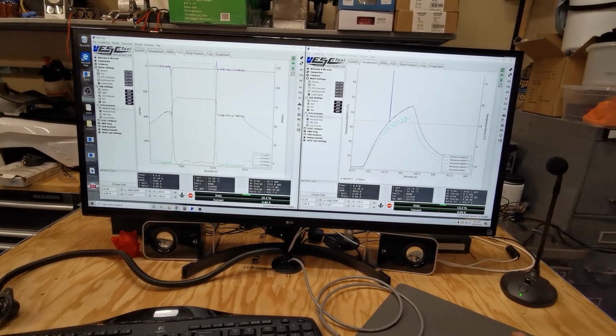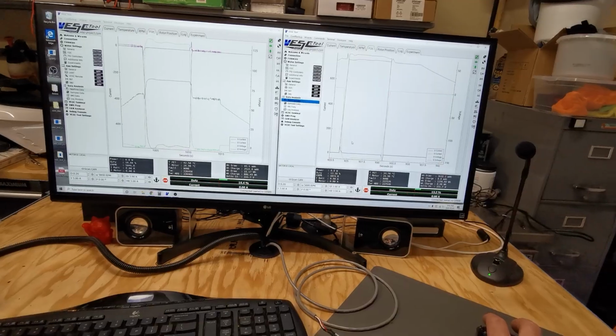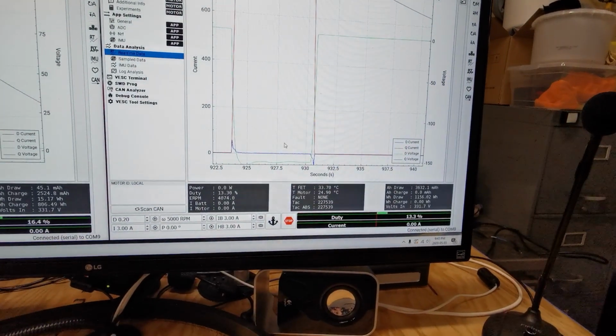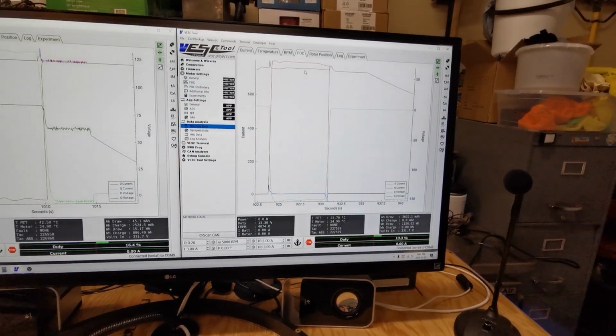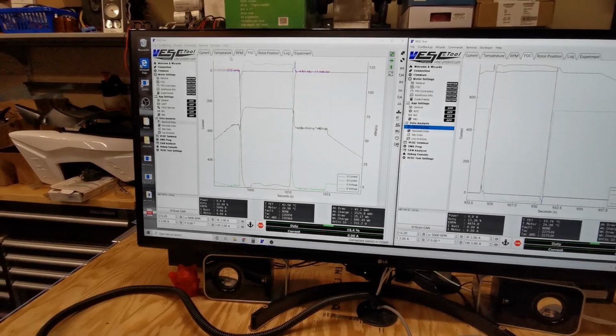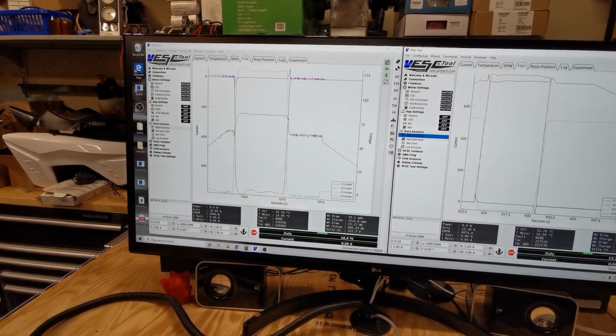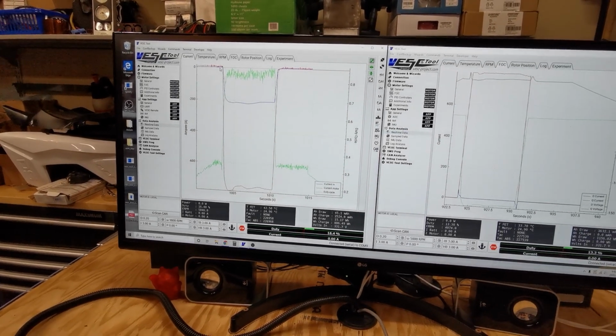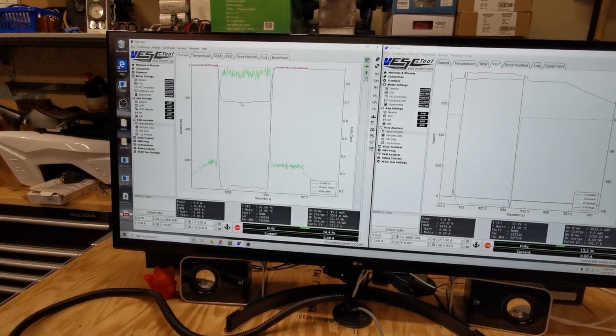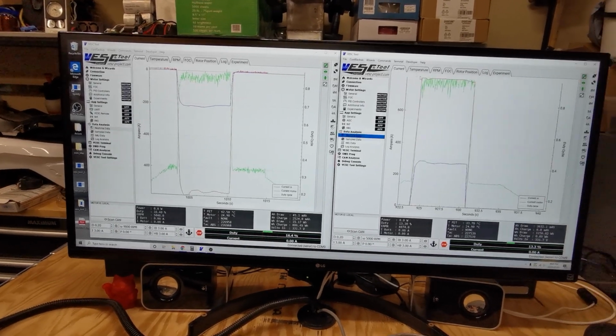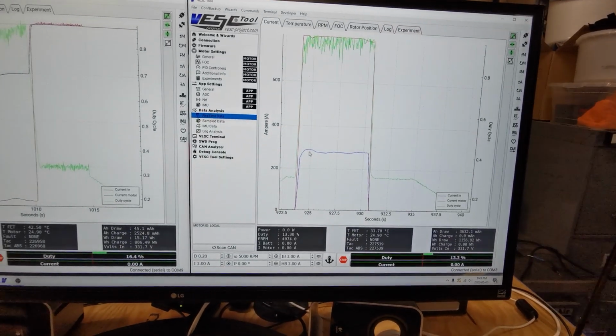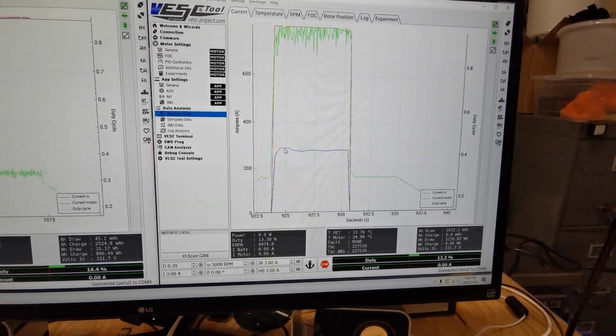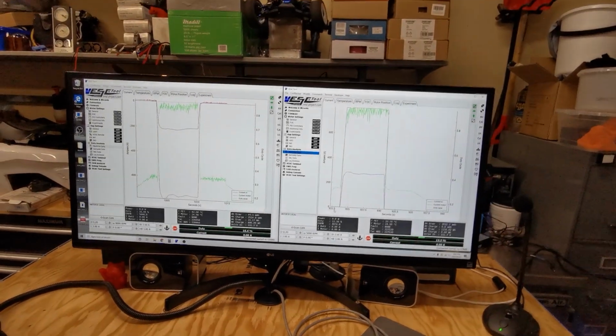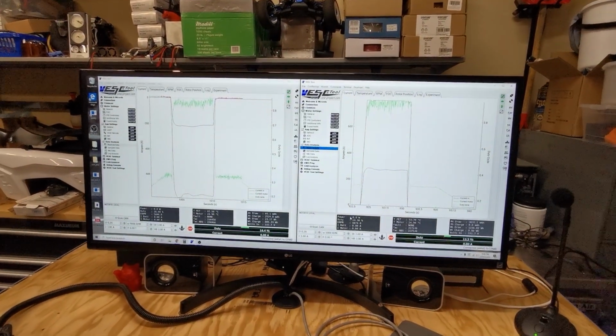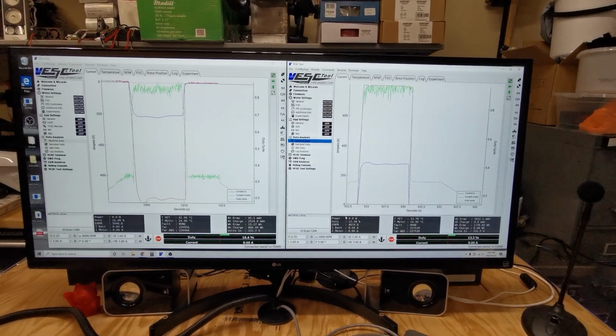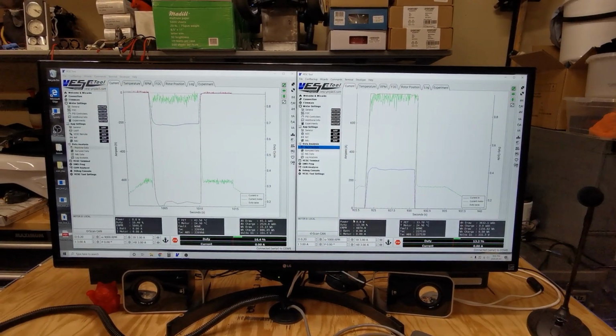Looking here into our FOC, we can kind of see the currents. You can see D-axis current stays at 0. We haven't enabled any field weakening or our maximum torque per amp yet. You can see the current here was just over 200 this time. That's regen current, and this current peaked just under 250 amps there. So that's not too bad. That's a pretty successful run. Seeing 80 something kilowatts there. That's pretty decent. I think we're going to call it quits for the night.